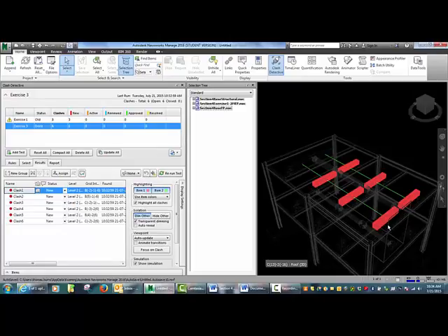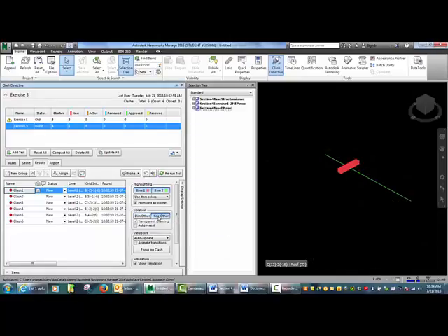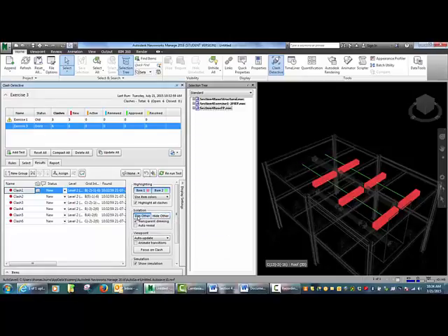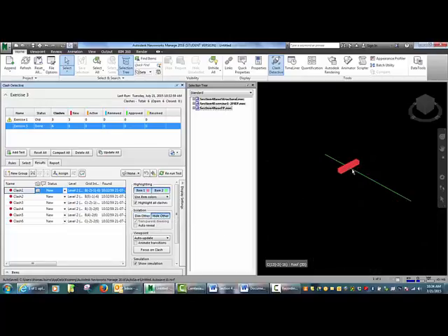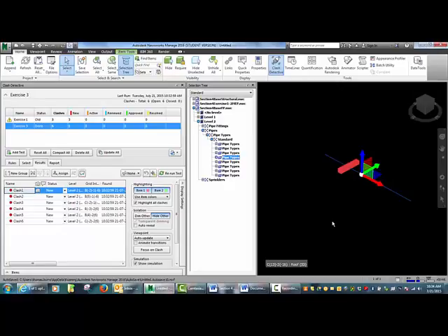So how many clashes did you find? There's 6. How many horizontal runs of pipes are involved? There's 2. And again, note the difference between hide other and dim other. What is the size of the pipe? I'm going to go to hide other because I'm going to have to select the pipe. When you select the pipe, you can look in the selection tree.